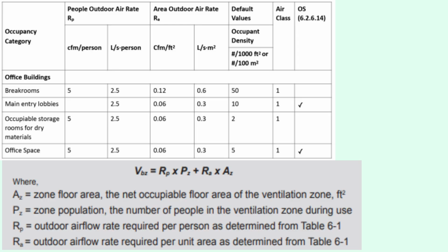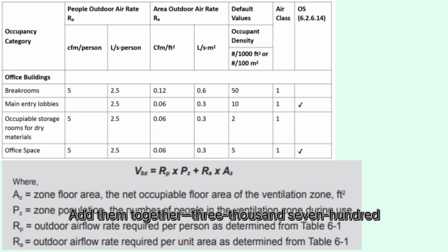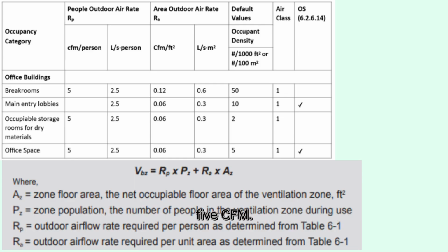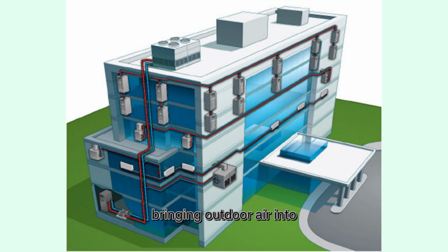We'll use the formula VBZ equals RP times PZ plus RA times AZ. For the office, 5 times 225 equals 1,125. 0.06 times 43,000 equals 2,580. Add them together: 3,705 CFM. Now the break room. 0.12 times 2,000 equals 240 CFM. Combine both spaces. 3,705 plus 240 equals 3,945 CFM. That's our total breathing zone outdoor air requirement, 3,945 CFM.